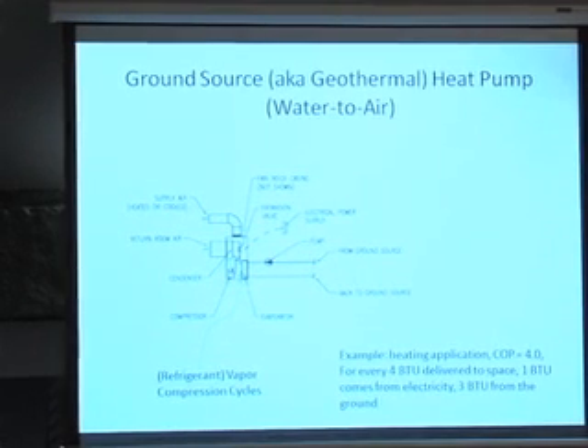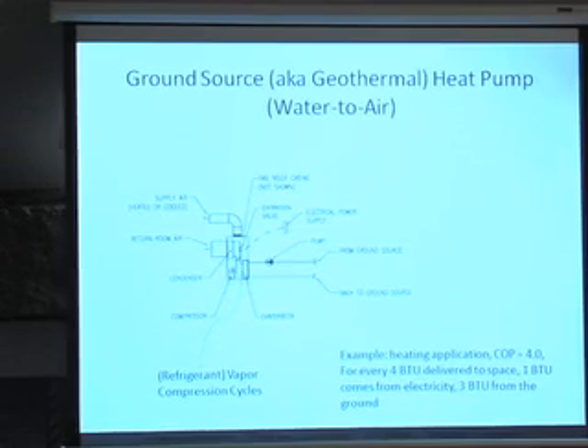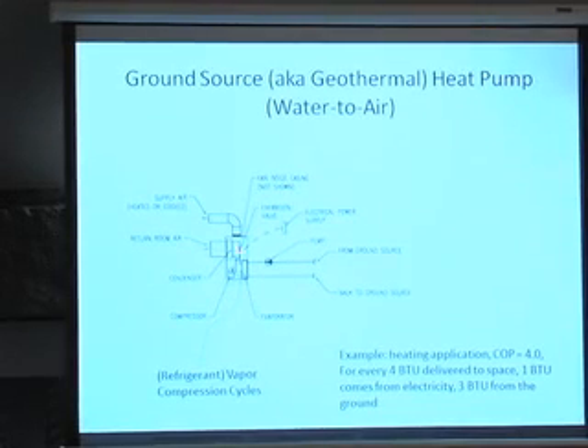Now, for example, for a heating application, if the heat pump has a COP of 4.0, COP means coefficient of performance. If you have a 4.0 COP, that means for every 4 BTU of heat delivered to the space, you use up 1 BTU of electricity and 3 BTU from the ground. So you can see it's very efficient.